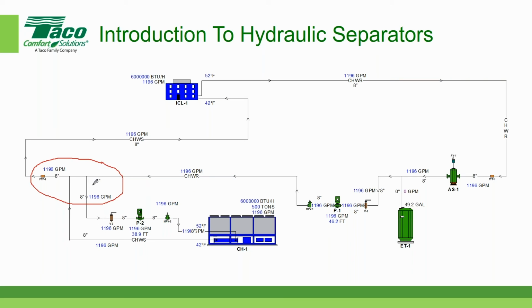this is, sometimes I refer to this as field built. In other words, most engineers will specify how they want the hydraulic separator or bridge to be constructed. And it's a bit tricky because when it comes to designing the bridge, it may not get installed precisely the way you design it because of a variety of field conditions. So we want to talk about an alternative. Rather than designing it from scratch, another option is to put in a pre-engineered hydraulic separator.